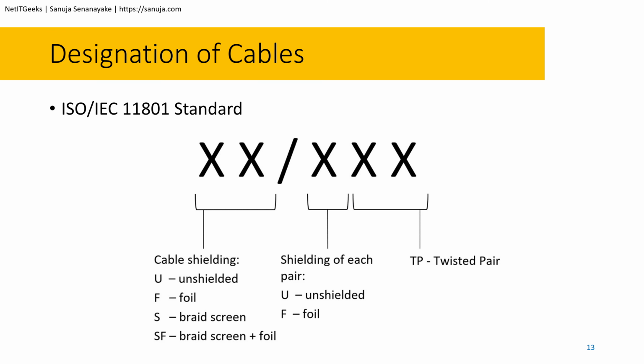When it comes to point designations of cables, it comes as a value like this: you'll have a U, F, S, or SF shielding type listed, then after the slash another letter like U or F for the inner shielding, and then TP, standing for twisted pair, indicating how many twisted pairs. So you'll have either U, F, or SF, then U or F, then TP. That's the ISO/IEC 11801 standard, and that's how we designate and identify cables. I won't go into full detail today, but I'll give you an introductory overview.